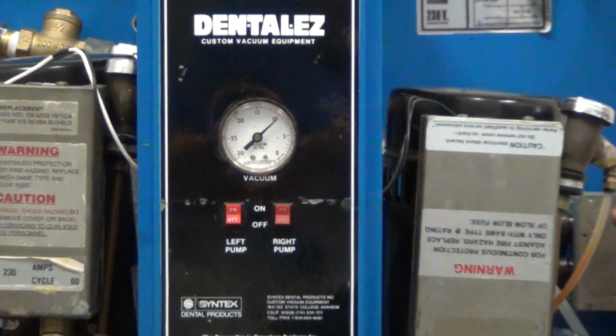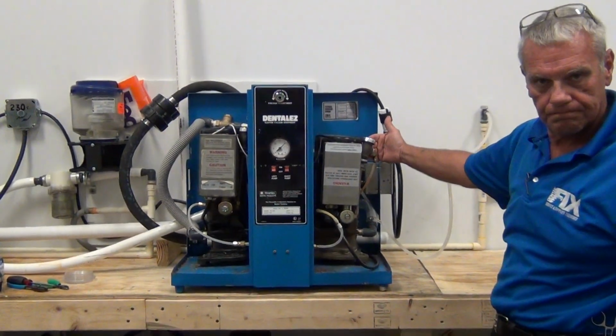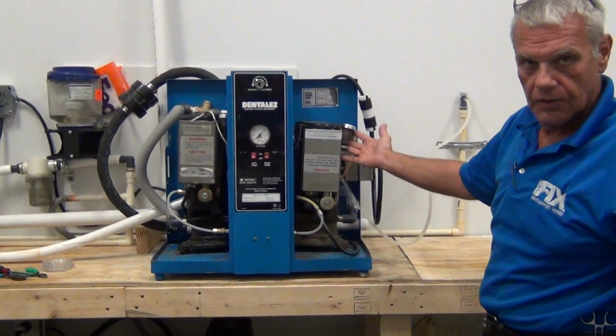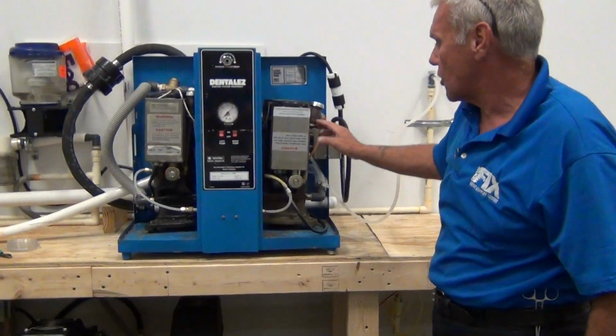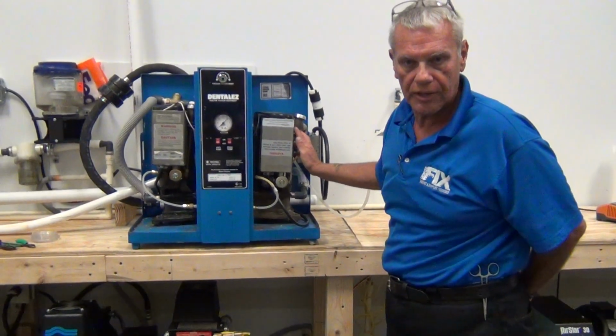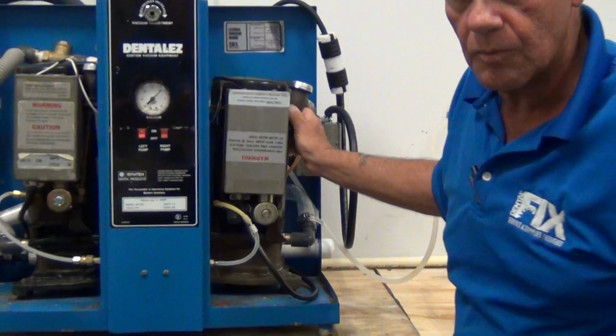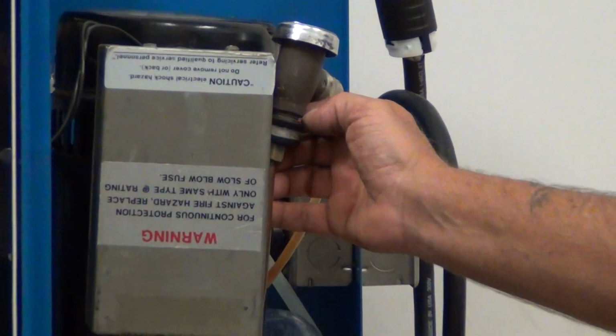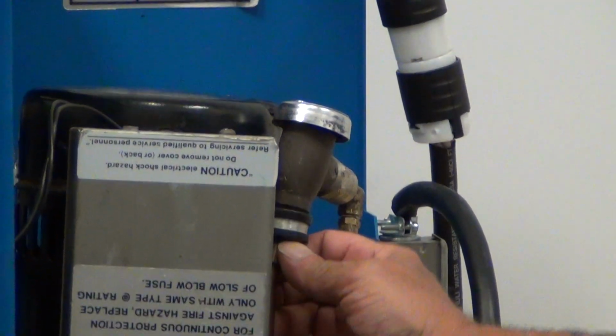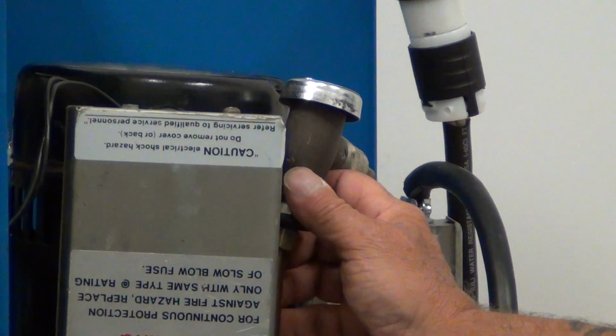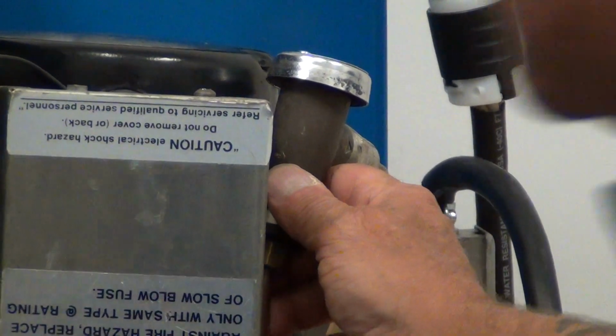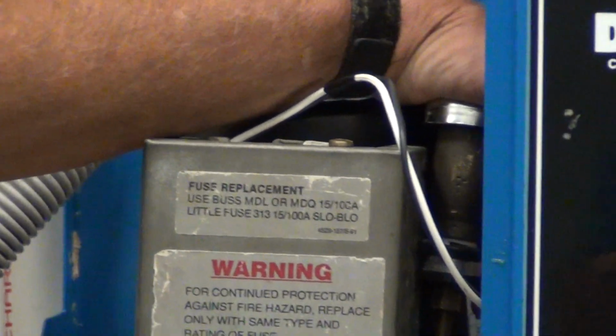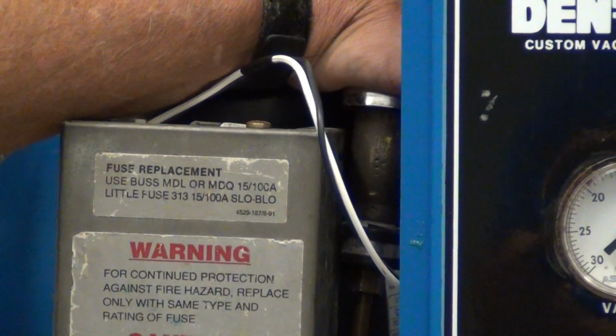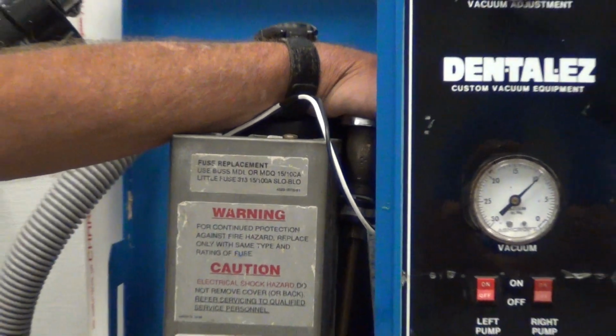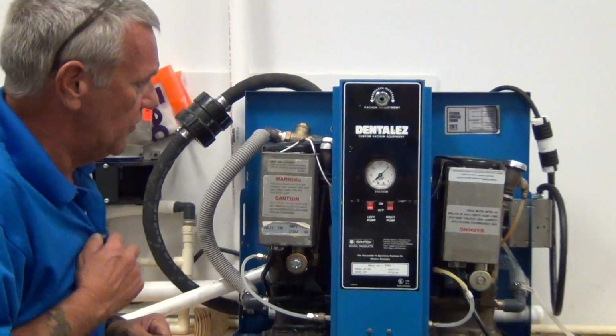Our next items to check are going to be our vacuum breakers. We want to check and make sure that there's no water stains or water leaking out of the vacuum breakers. These are a very high replaceable item. I believe you've all probably got some in stock. If you don't, they're available from us or available from DCI through us. We're going to check both vacuum breakers. They look fine. I don't see any water stains, any calcification, any active leaking whatsoever. Now, let's move on to our next item.